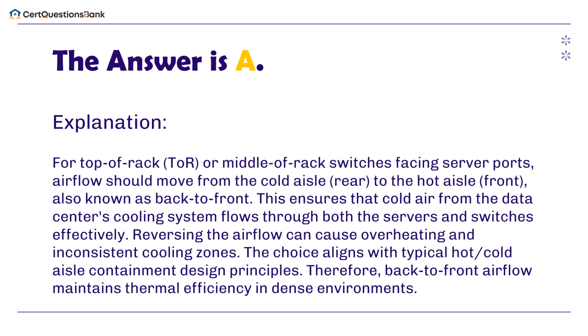This ensures that cold air from the data center's cooling system flows through both the servers and switches effectively. Reversing the airflow can cause overheating and inconsistent cooling zones. The choice aligns with typical hot/cold aisle containment design principles. Therefore, back-to-front airflow maintains thermal efficiency in dense environments.